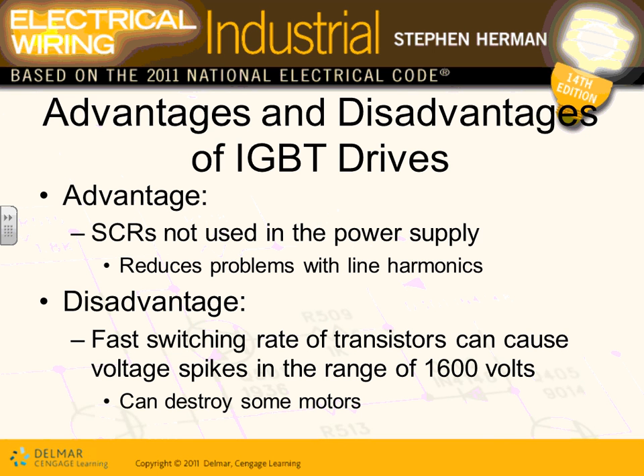So their advantage over SCRs, guys, and their problem, look at that, is that because they flip so fast, they can have a pulse of 1600 volts. So it creates transient issues in your system that you have to deal with. IGBTs. Any comment, guys, about the IGBTs, SCRs?